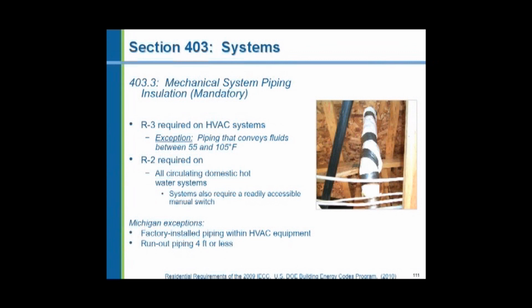where you would have valves, pressure relief valves, unions, all sorts of fittings that would be difficult to insulate. So the code says that you can not insulate the piping for a distance of up to 4 feet away from a boiler or a chilled water coil or a heating coil if it's difficult to do so with all of the valves in place. Please do not insulate unions. Pipe unions must be left exposed for the service person, so in no case do you insulate the union.